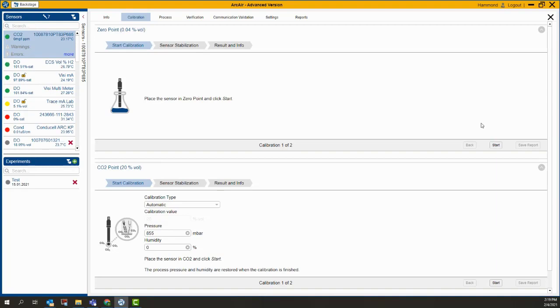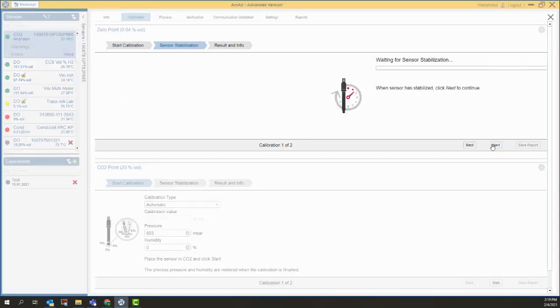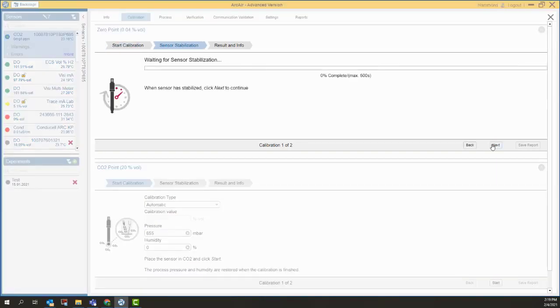So I've got a sensor connected right now, and I'm going to start my calibration here. And let's wait for it to stabilize, and it'll start its process here. Now, it should be noted that it's good to wait the full time period here. So this calibration is a little bit longer than what you see for other sensors like our VisiFerm. So it's a max here of 500 seconds. So I'm going to let that run for a little bit, and then we'll come back.